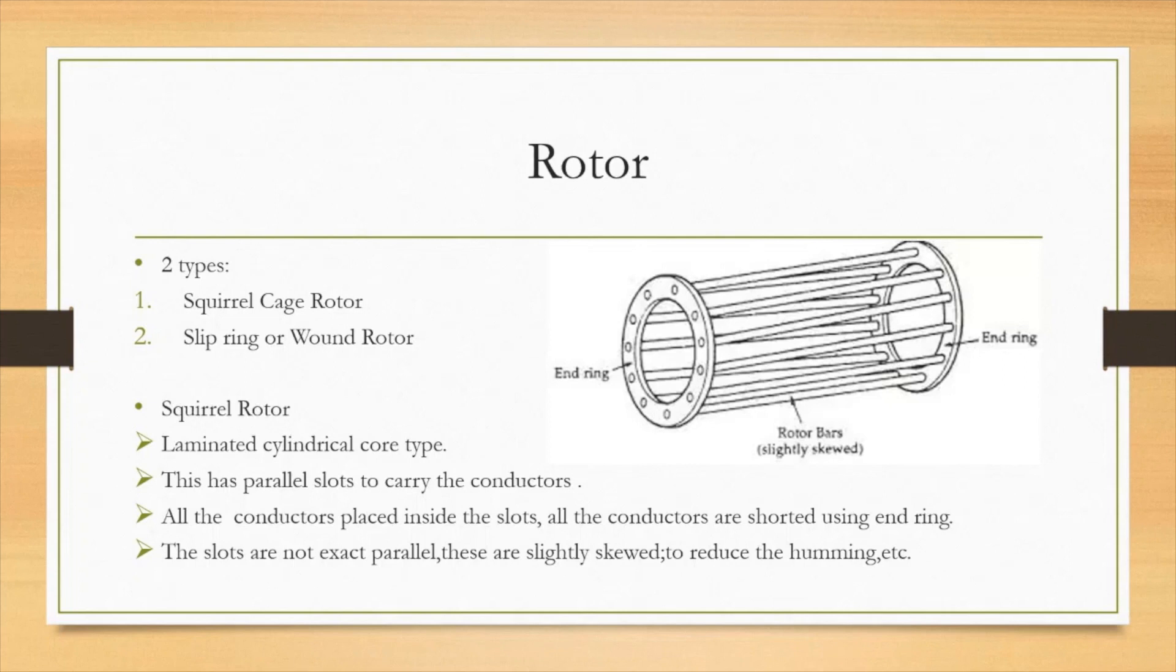In this squirrel cage rotor, this is laminated cylindrical core type with parallel slots to carry the conductor. All the conductors are placed inside the slot and shorted using the end-rings. We can't add external circuit and resistances to this because it is shorted using end-ring. The slots are not exact parallel. You can see this in this diagram. These are slightly skewed to reduce the humming and noise.